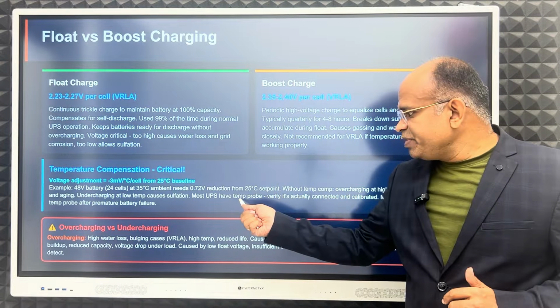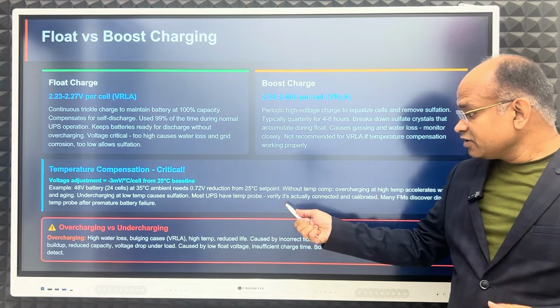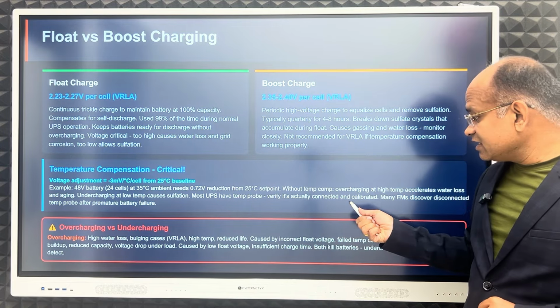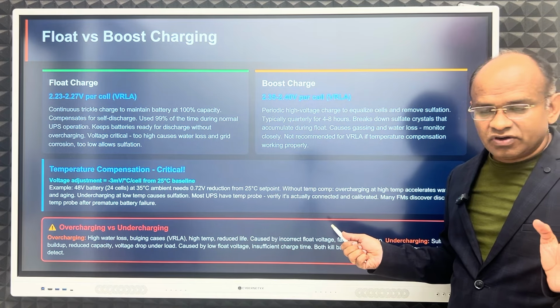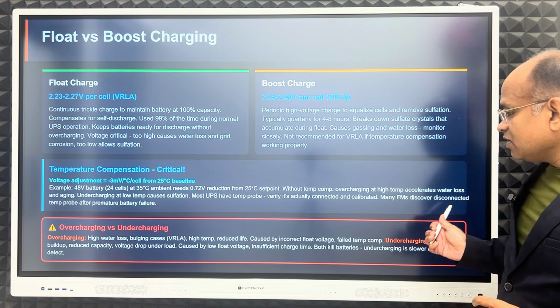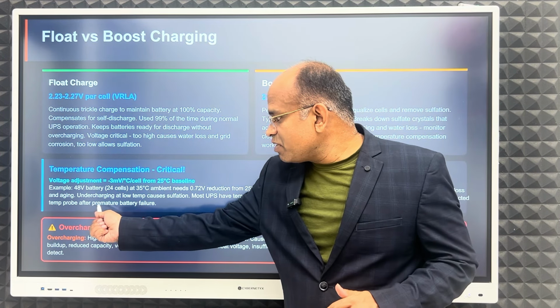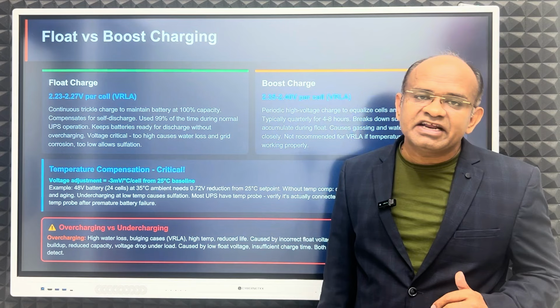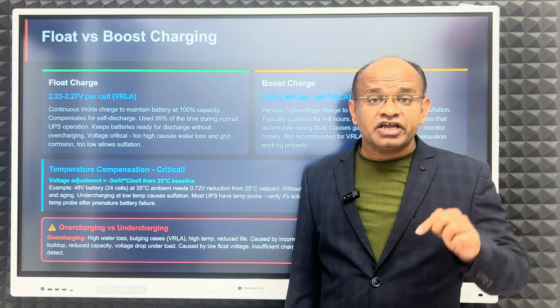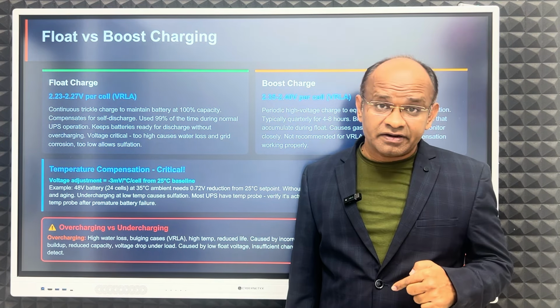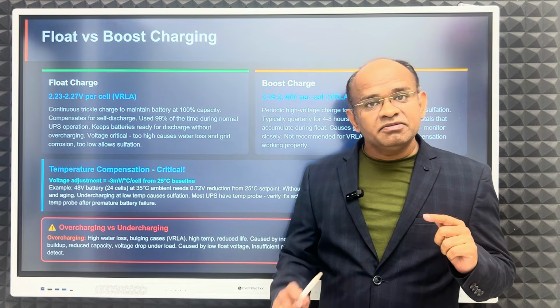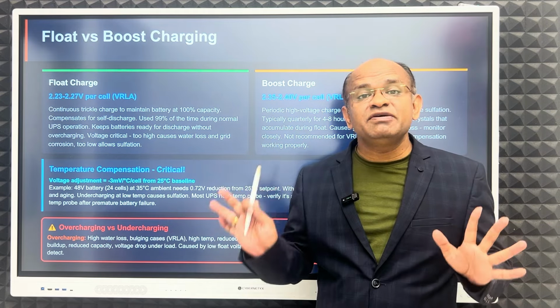Most UPS have a temperature probe; verify it is actually connected and calibrated. Many FMs discover a disconnected temperature probe only after premature battery failure. So just check that the probe is there. It should not be disconnected, because the UPS uses its feedback temperature.